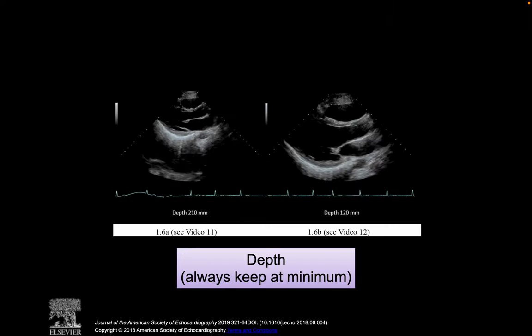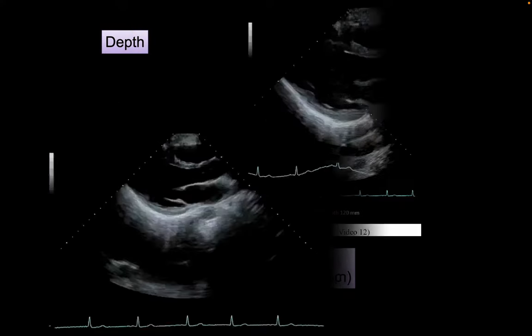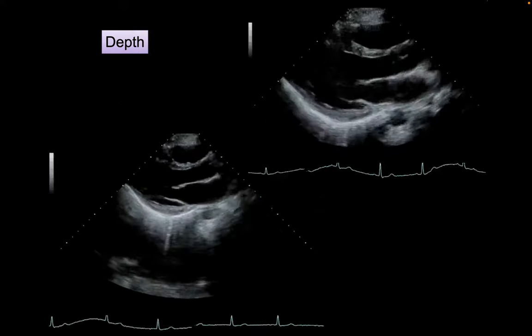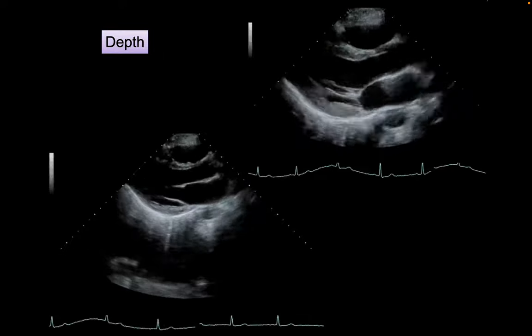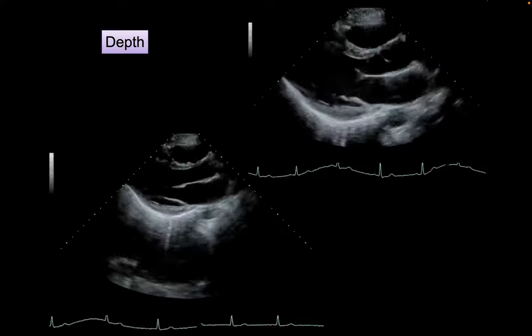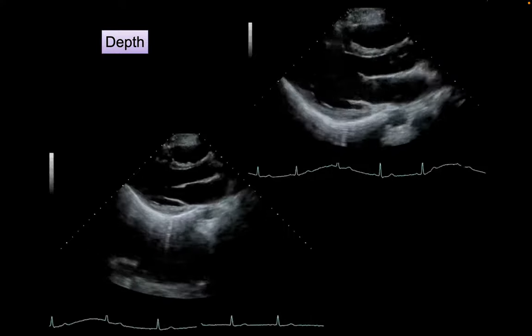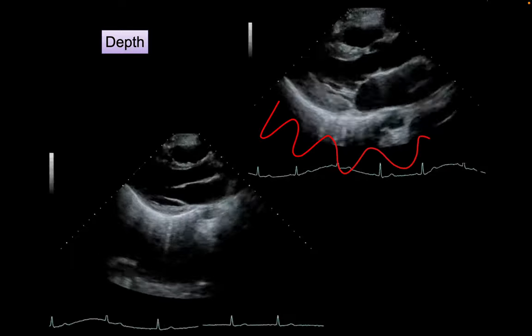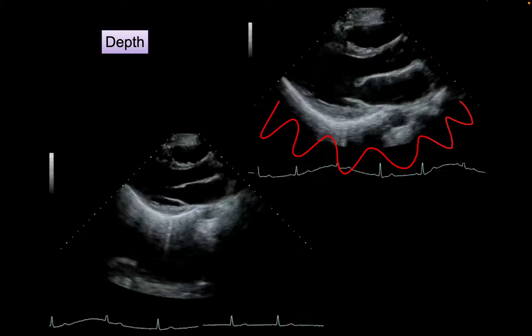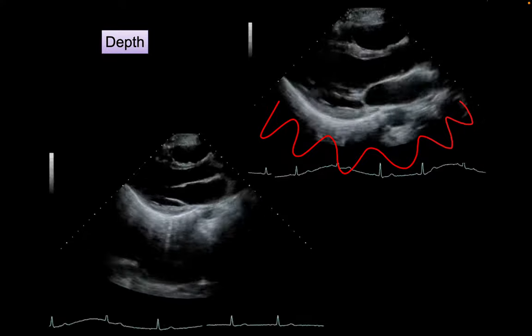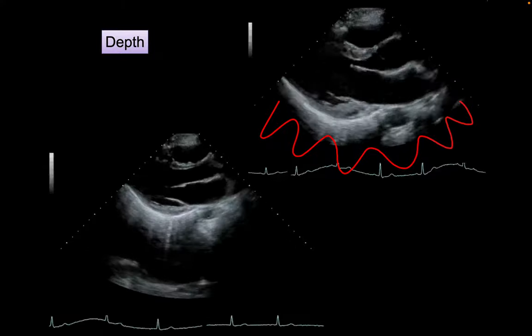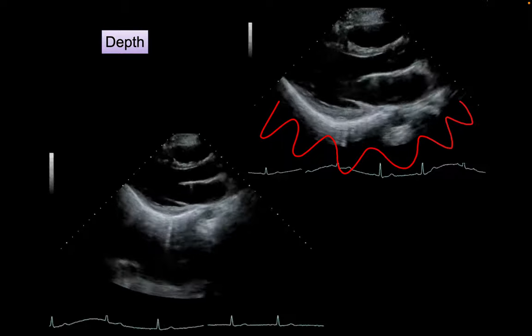Depth, I mentioned depth many times during the previous lectures. You really have to keep your depth at the minimum. Depending on what you're imaging, you don't want to waste most of your screen, most of your computing power to look at something that you're not interested in. So you should always use the minimum depth, meaning that whatever you're looking at should be centered on your screen, and there shouldn't be too much behind it so that you're not wasting your ultrasound machine computing power.